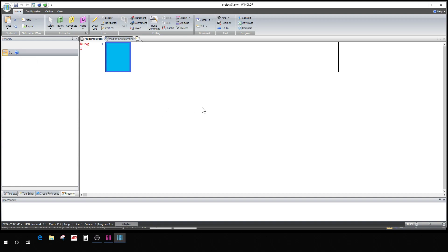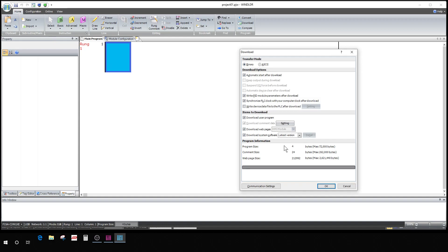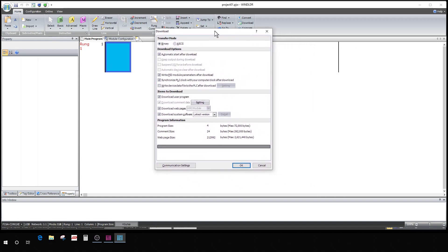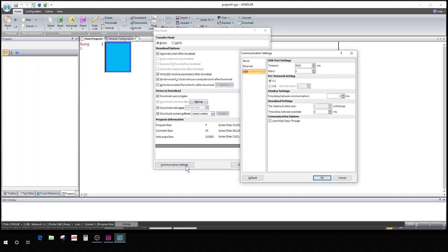Now you're communicating USB. You have to have the USB cable plugged up to update your firmware. You can't do it over ethernet. Have your USB cable connected to your PC to your PLC. Now that you've got it set on USB, you go to download. You want to make sure this box is checked: download system software. If that's not checked you're not going to update your firmware.